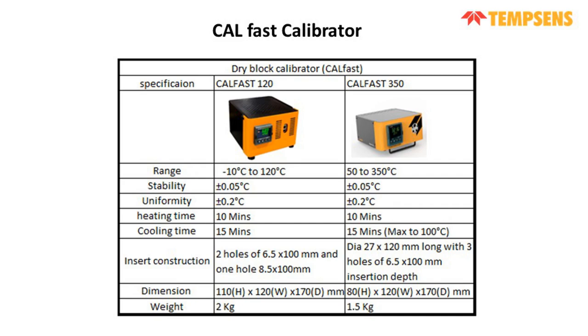Then we have CalFast 350. The temperature range is 50 to 350, and stability is plus minus 0.05, and uniformity is plus minus 0.2 degrees centigrade. Again, the heating time is very fast, 10 minutes, and cooling time is 15 minutes. It has 120 of immersion depth, and the weight is just 1.5 kgs.